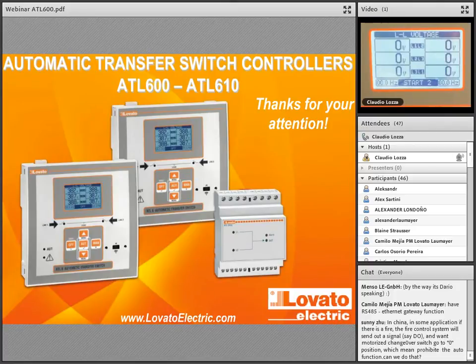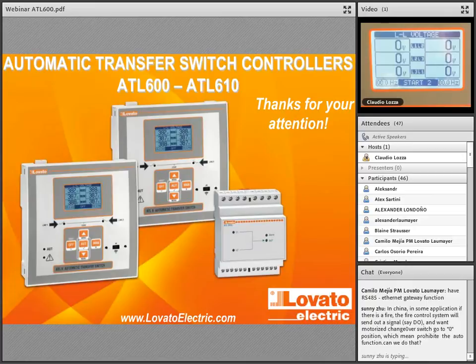Sunny Zhu from China asked: in some applications, if there's a fire, the fire control system sends out a signal, and we want the motorized changeover switch to go to the 0 position, meaning prohibit the auto function. Can we do that? Yes, you can use a digital output, since all the inputs and outputs are user definable.